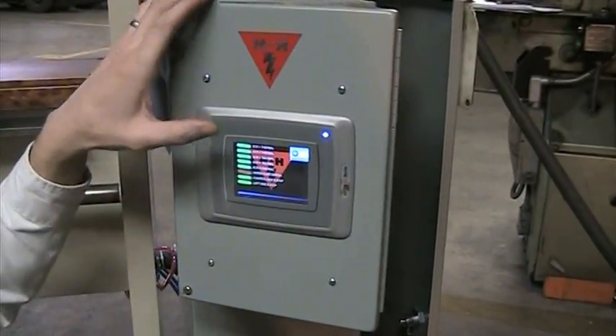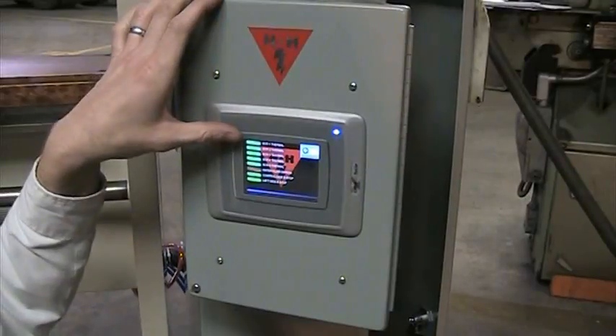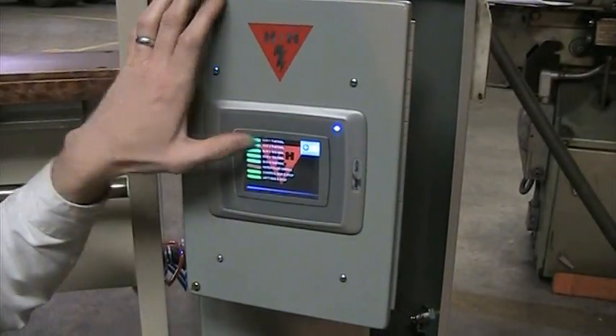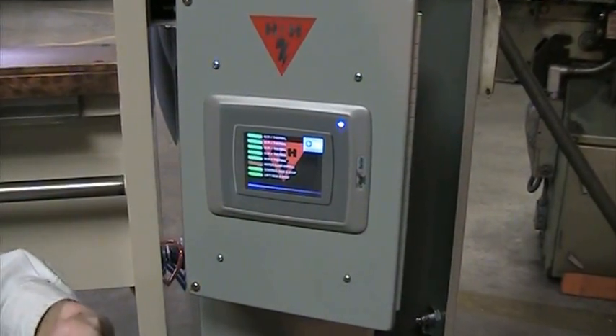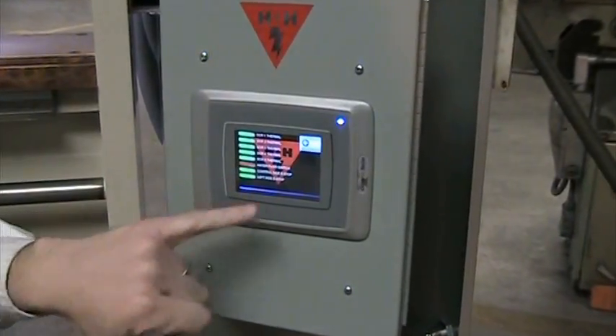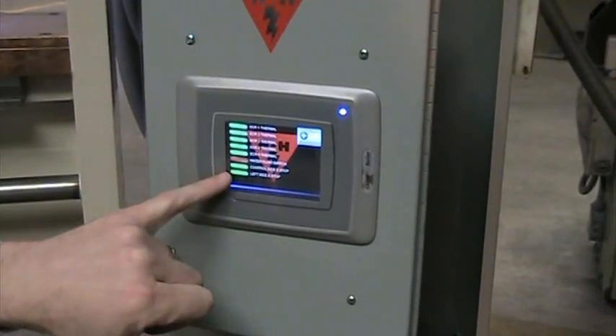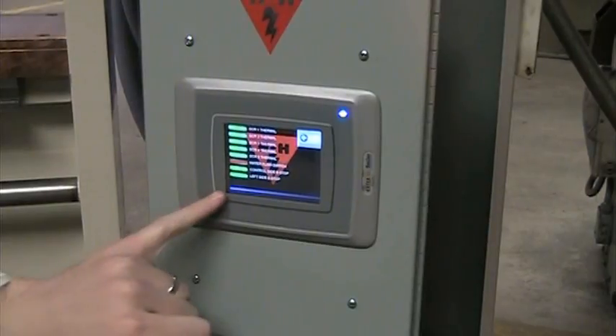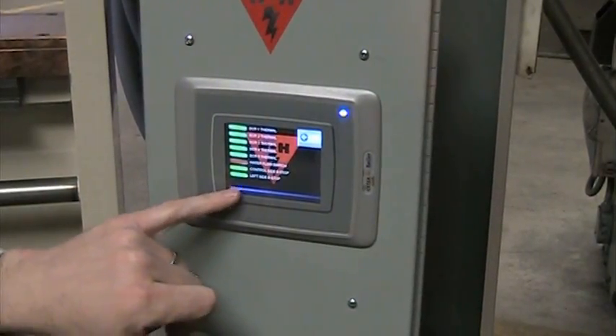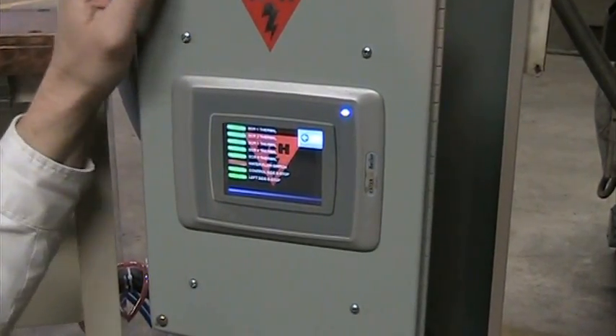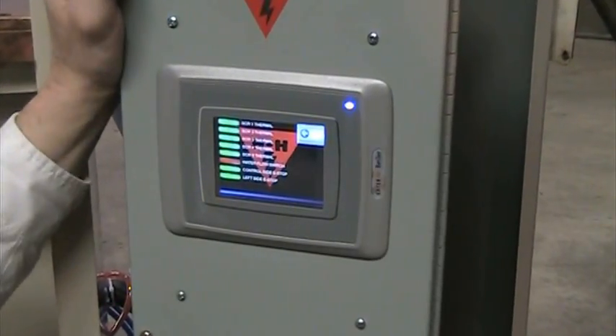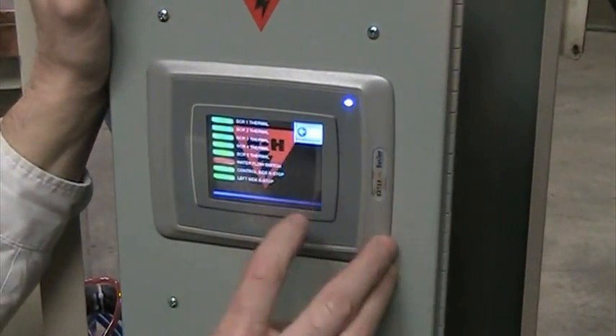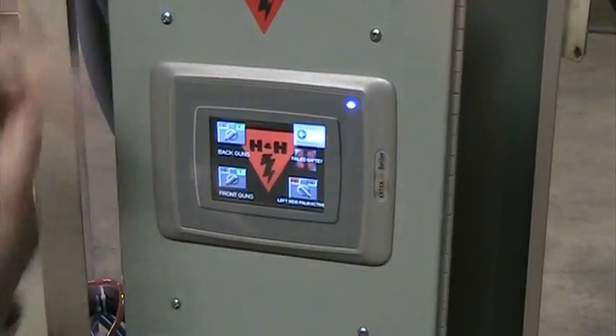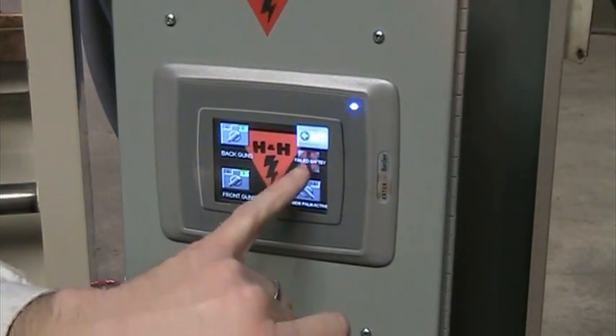From top to bottom, we have SCR thermal number 1, thermal 2, 3, 4, 5, a water flow switch, which currently I have the water off, so the switch is red. Control side e-stop, which is green, which means it's in the up, ready to go position, and the left side e-stop, which is in the up, ready to go position. So right now, if I were to try to initiate the machine, nothing's going to happen. And if we'll go to the operator screen, you can see the failed safety in bright red.